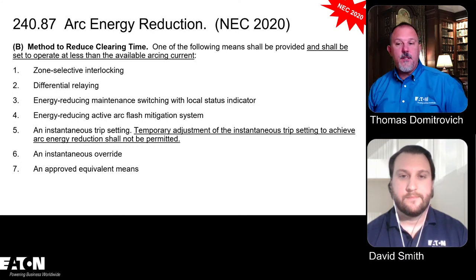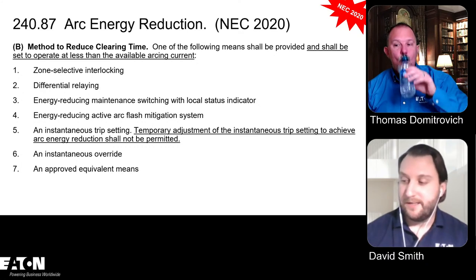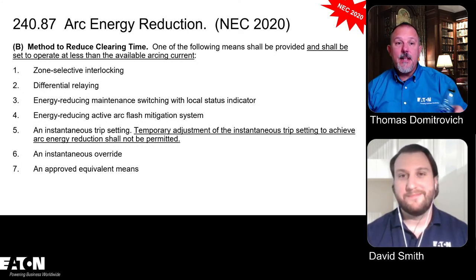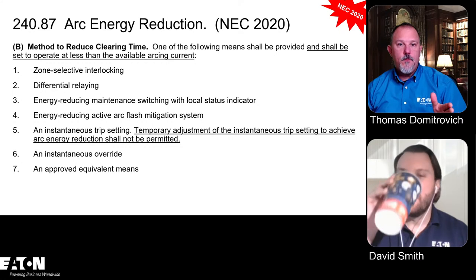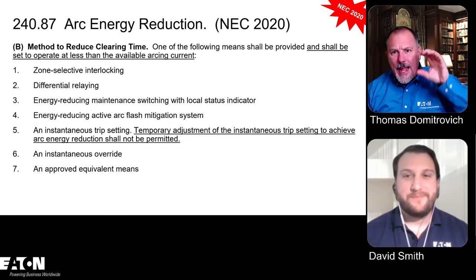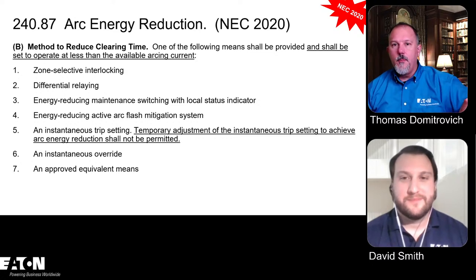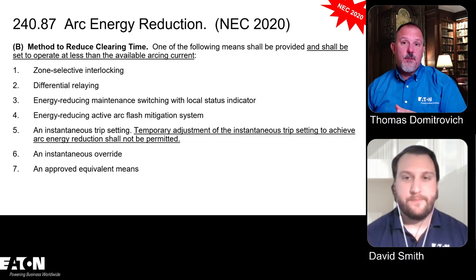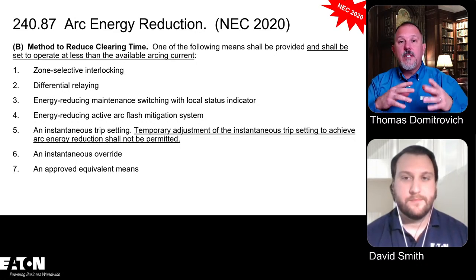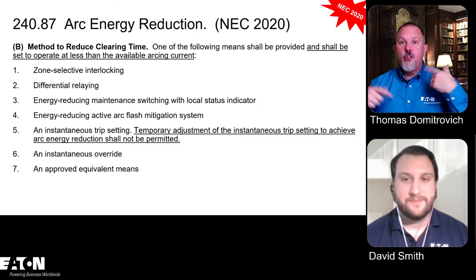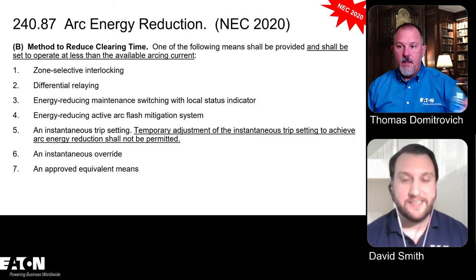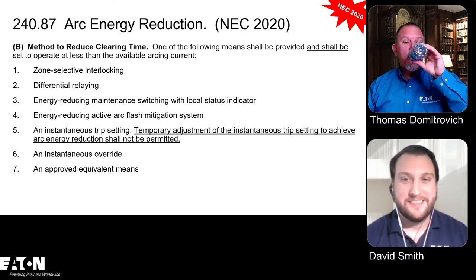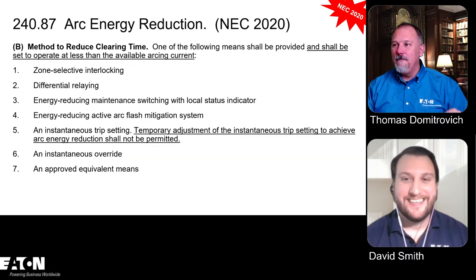Do you know what an instantaneous override is on a breaker, David? If it's an override, that is instantaneous. Exactly. And it's on every molded case circuit breaker. It's not adjustable. It's an analog circuit that doesn't require a brain. It just basically says the breaker goes when your fault current gets greater than this number, without an intentional delay. It's faster than the instantaneous because the instantaneous has to use the brain to determine the tripping. Ladies and gentlemen, we're talking about faster than instantaneous. That's right. That's incredible. How about that for marketing? How about them apples, huh?